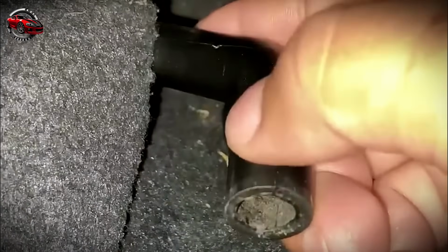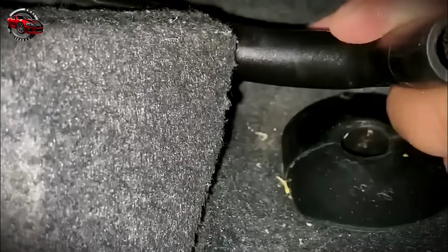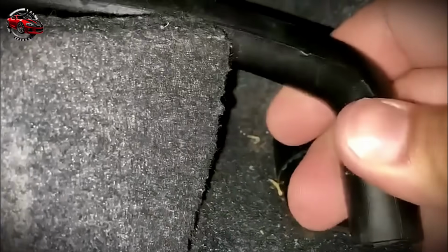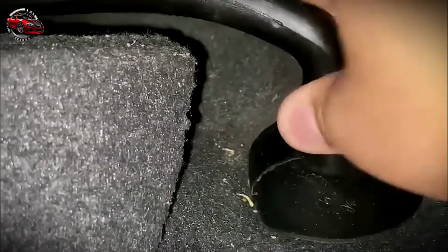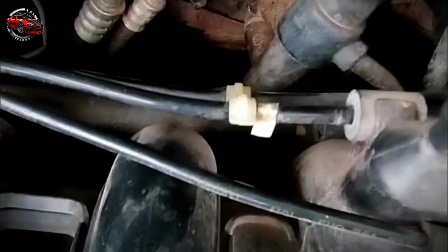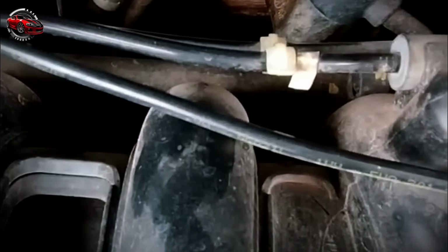If it's stubborn, poke something soft up in there: a plastic zip tie, a piece of thick weed trimmer line, a plastic straw. Never use a metal pick or a screwdriver. You can nick the rubber, or worse, puncture the plastic drain pan or the evaporator core itself. You're just aiming to break loose that little plug of dirt.